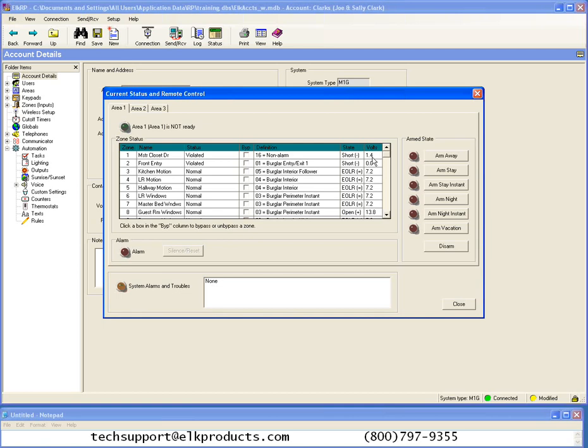Alternately, there are some other devices that do like a dial capture that basically connect to where a phone line would connect on the panel. They make the panel think there's a phone line there and just capture the data coming out of the dialer. Telguard is one that has that. There are others, so you can use something like that as well. So those are the primary options you would have, either through the serial expander with Uplink or AES, and then the other option would be a dial capture device like the Telguard.